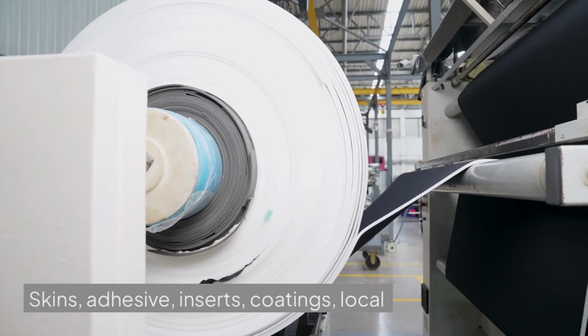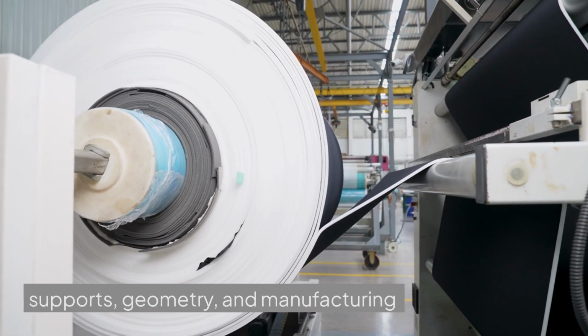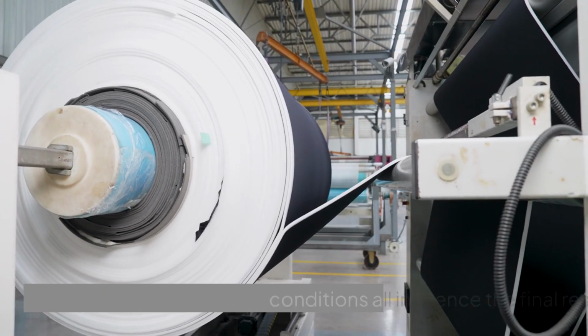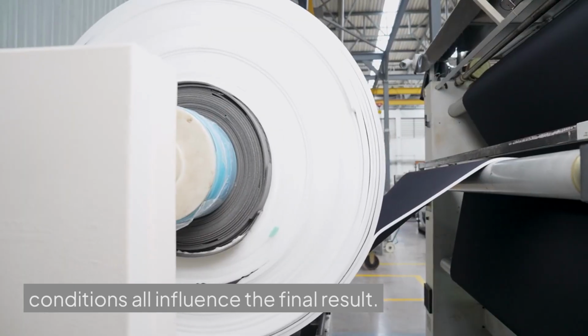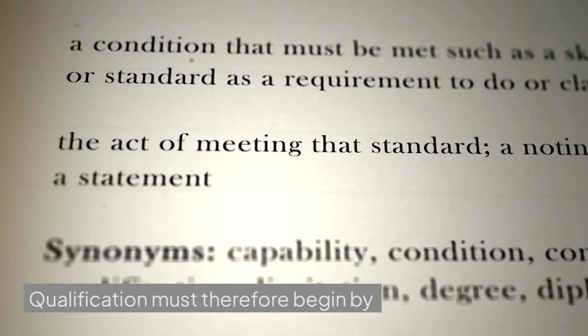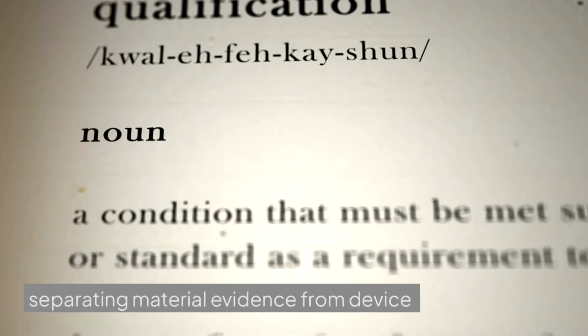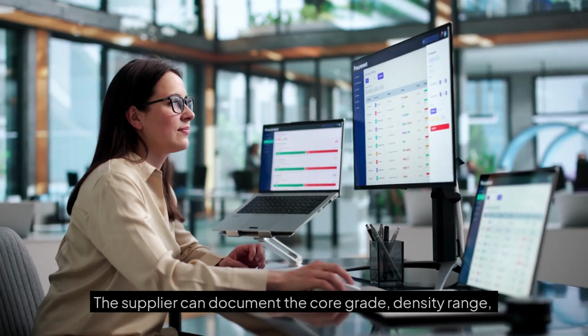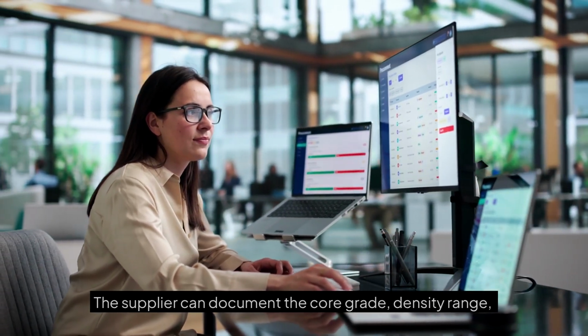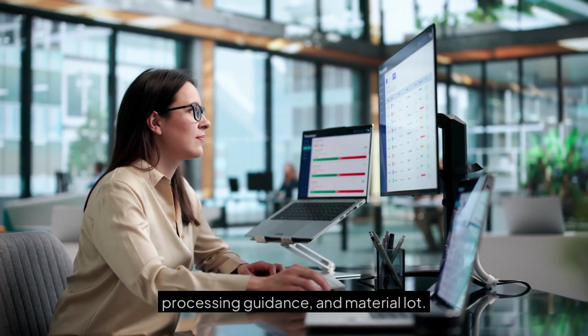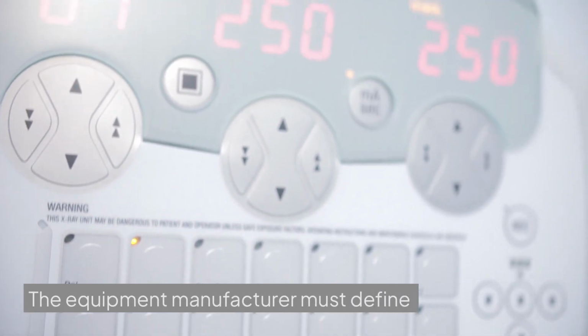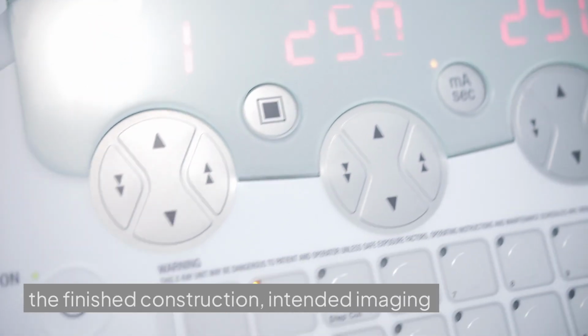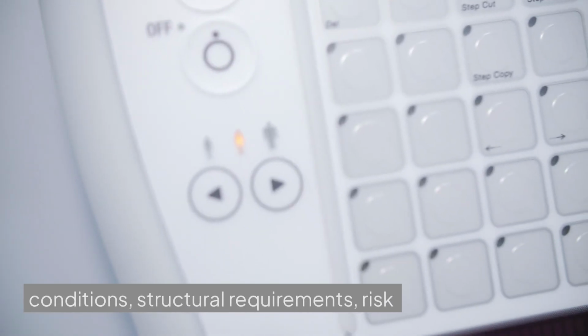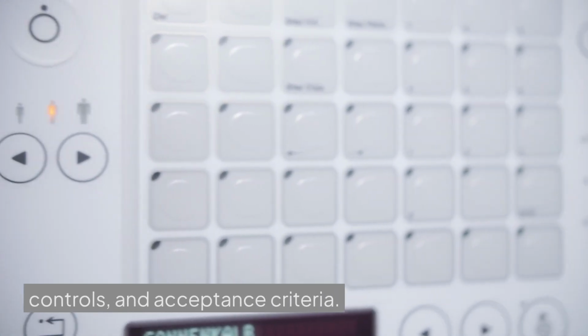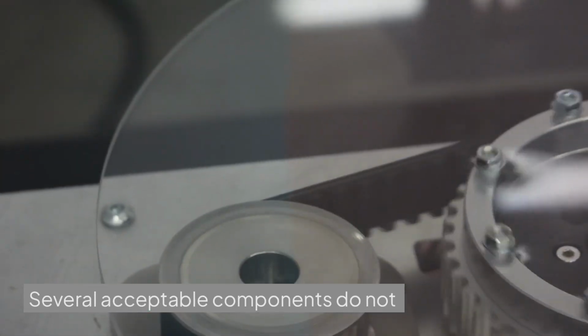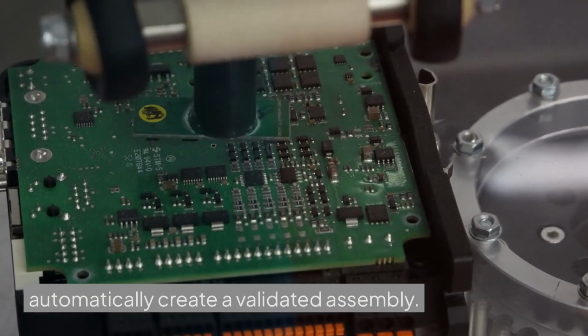Skins, adhesive, inserts, coatings, local supports, geometry, and manufacturing conditions all influence the final result. Qualification must therefore begin by separating material evidence from device evidence. The supplier can document the core grade, density range, processing guidance, and material lot. The equipment manufacturer must define the finished construction, intended imaging conditions, structural requirements, risk controls, and acceptance criteria. Several acceptable components do not automatically create a validated assembly.